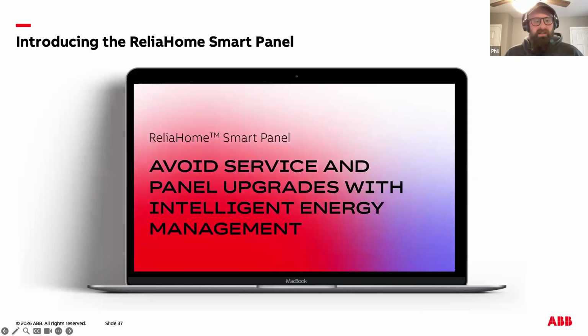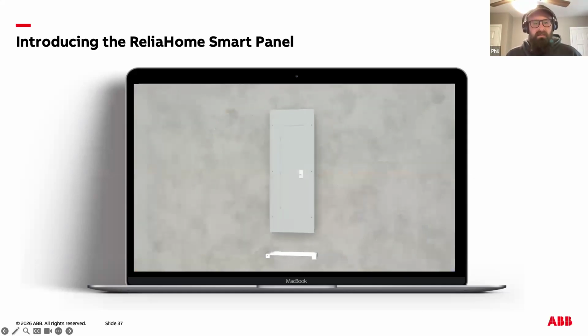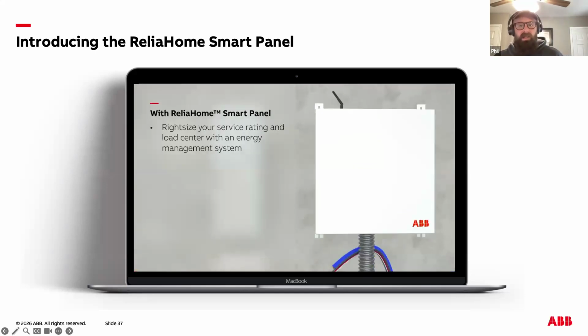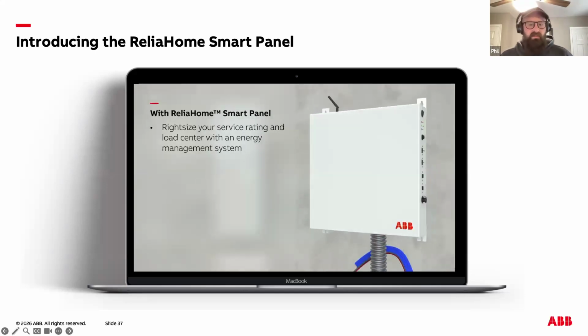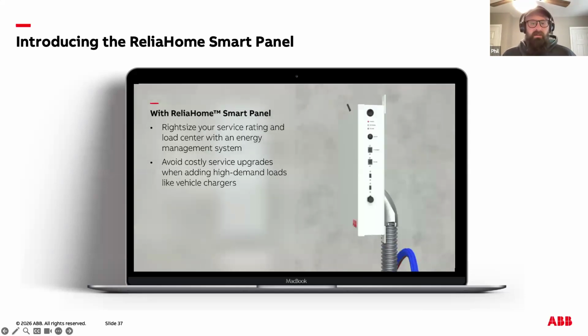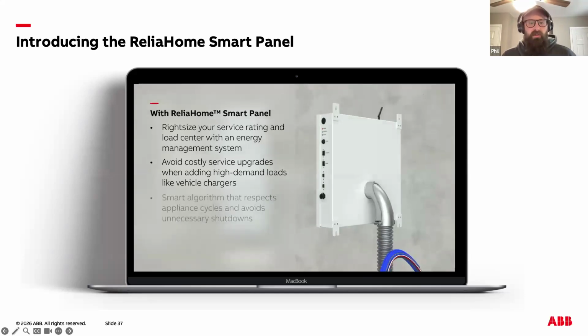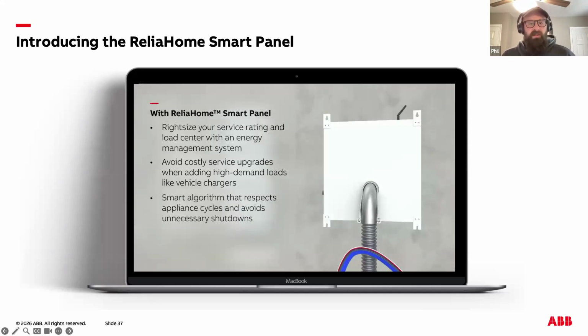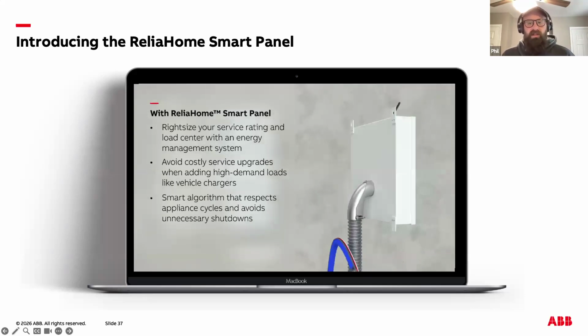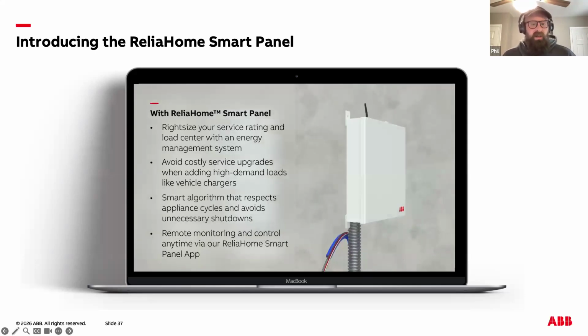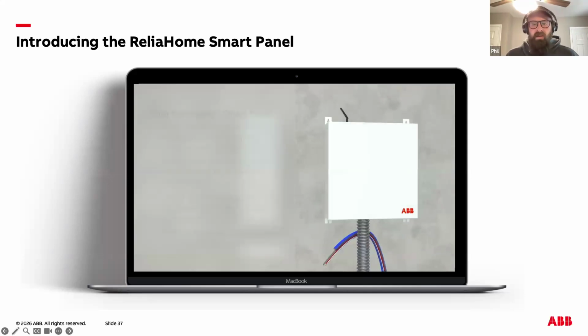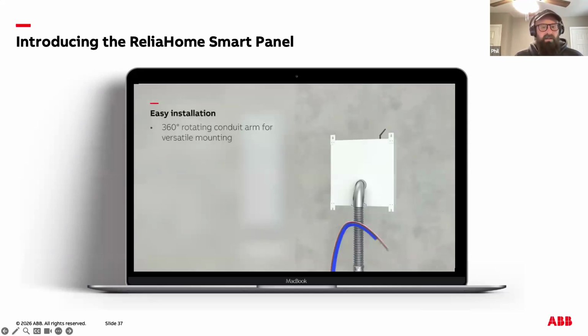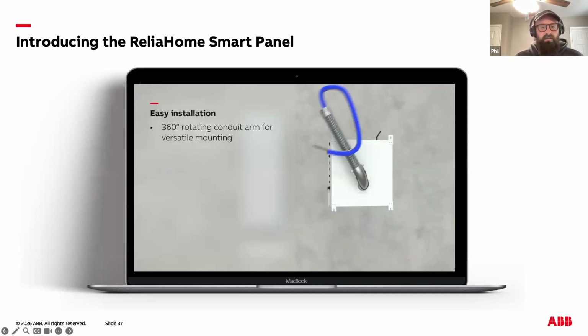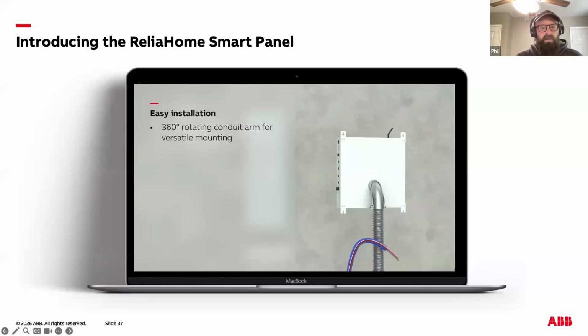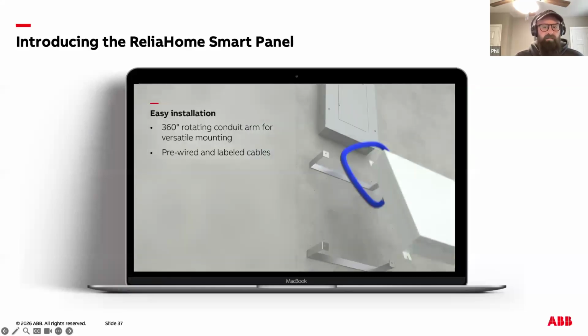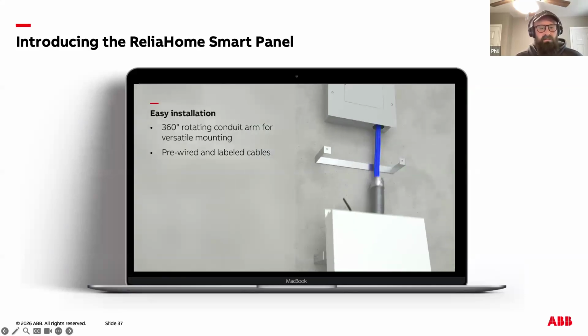Some of you may recognize this as the Lumen Smart Panel. Lumen was acquired by ABB back in January of 2025. The ReliaHome Smart Panel is a 12-pole controller. Out of the 12 poles, 6 are rated for 30 amps and 6 are rated for 60 amps with 10 and 6 gauge wire respectively. It connects to the home's existing load center and can control up to 12 120 volt loads, or what we typically recommend, 6 240 volt loads.